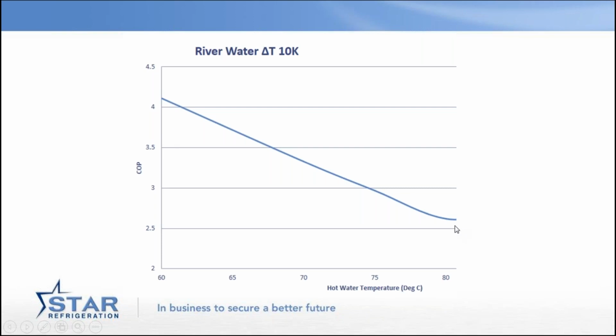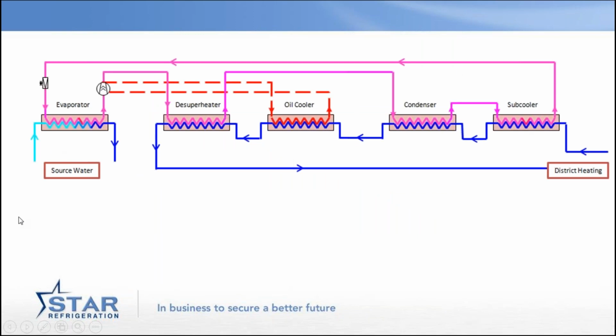And frankly, one of the techniques that's really well deployed in Norway is this ability to flex the temperature. The heat network does not have to be at its design temperature every day of the year. So they're varying from around 95 degrees down to about 75 degrees over the course of a heating season. They need some heat every day of the year because they're producing the hot water, but it's about flexing that.